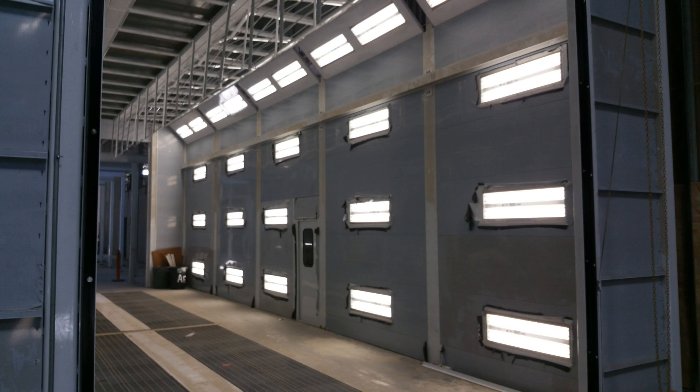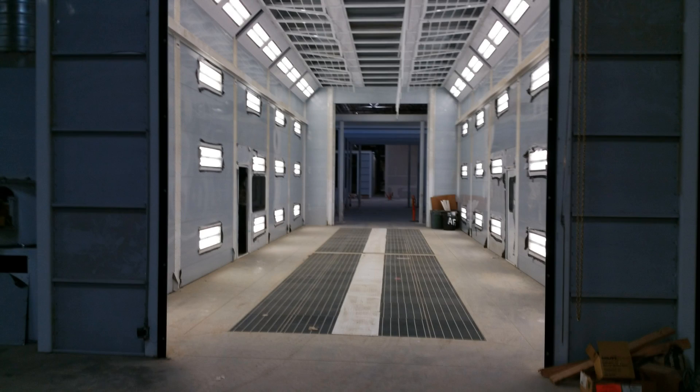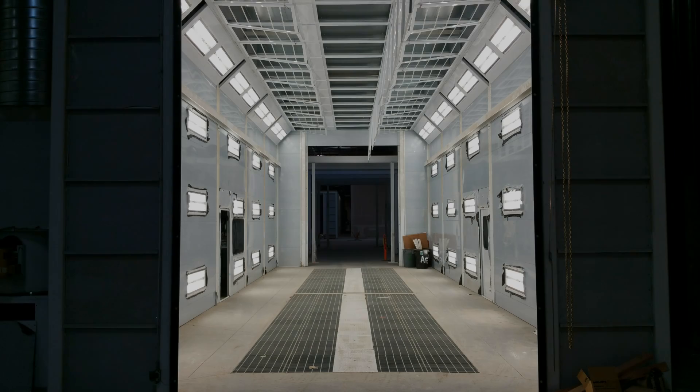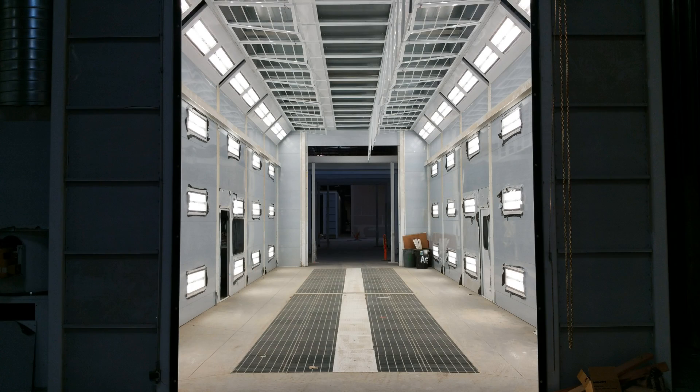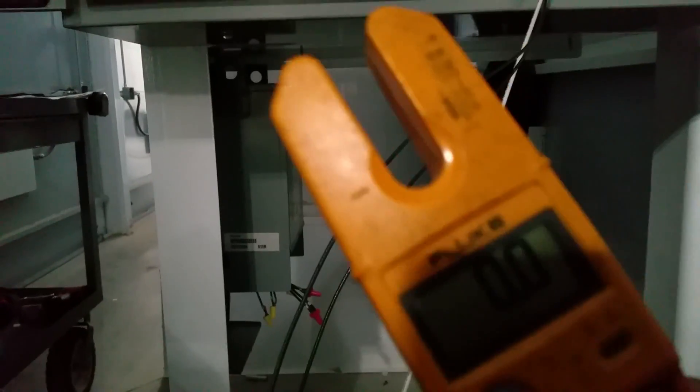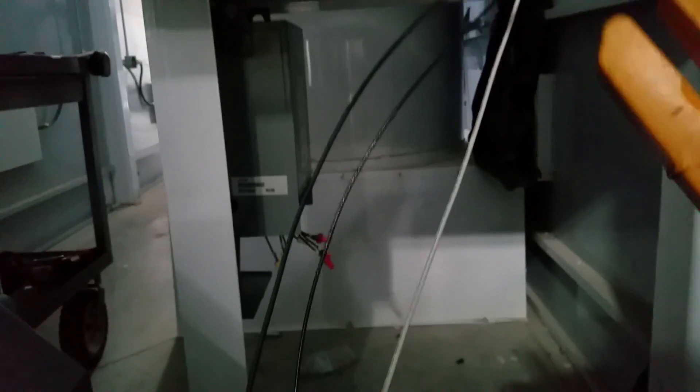The photographs you're seeing are a spray booth and it's wired in left and right sections and we're just running it temporarily off a generator and this gives a perfect opportunity to see how left and right halves behave with a common neutral.